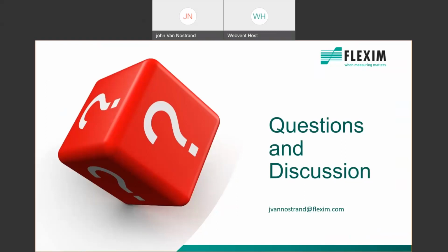All right, great. Can we also receive the temperature signal via HART? Yes, you can. That's a very good question as well. We do offer HART, and that parameter is available on the HART string. All right, great. What is the lowest concentration of sodium hypochlorite in water that can be detected with the FLEXIM meter? Less than 1 to 5 ppm? Yes, 1 to 5 ppm is certainly possible.